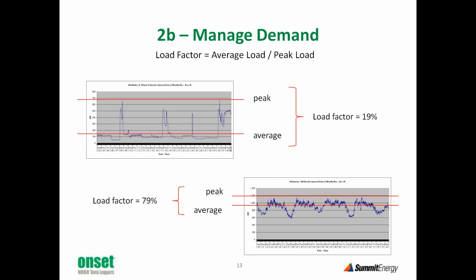Now, we think in terms of load factor, and this slide shows the definition of load factor, which is the average load divided by the peak. So in the first graph on the top, we see a 19% load factor, relatively low, because the average usage is down around 150 kilowatts, but the peak is almost 700. If you could level that out, as we've shown in the second graph, load factor 79%, here the peak is not a whole lot higher than the average.